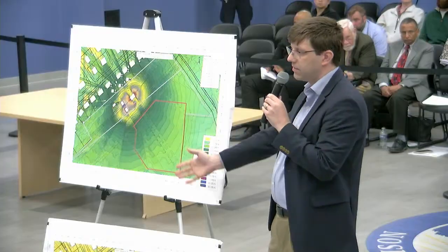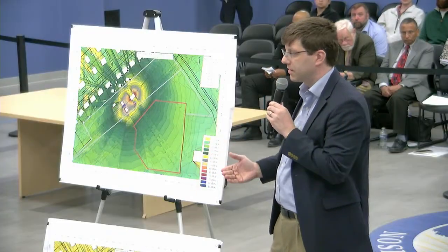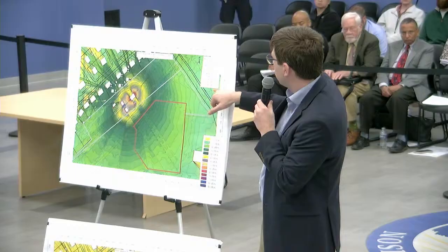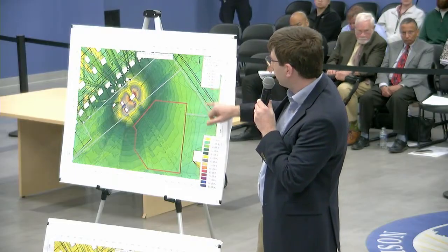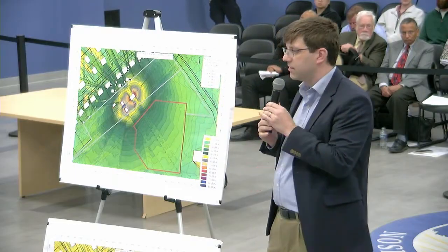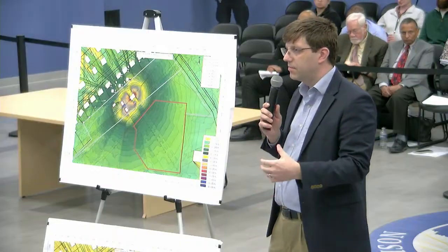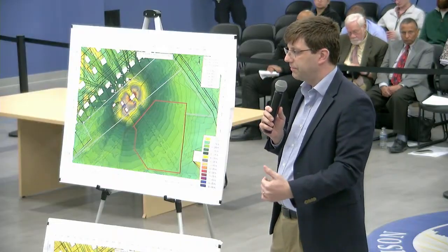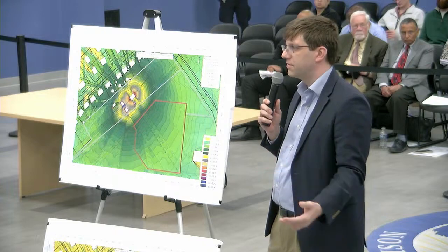So if we include all the worst case HVAC noise from the existing substation, our sound emissions at F, the worst case, are 44 dBA. This includes not only the transformer noise, the hum, the noise from the fans, but also the worst case noise assuming all the HVAC at the site is on.